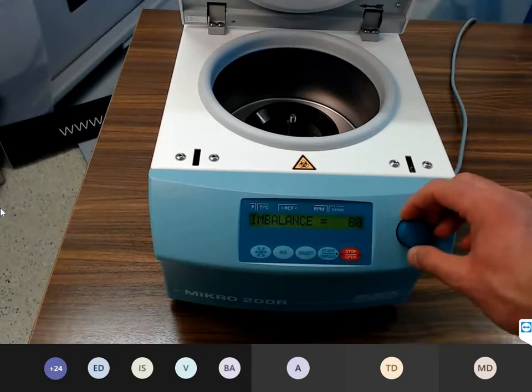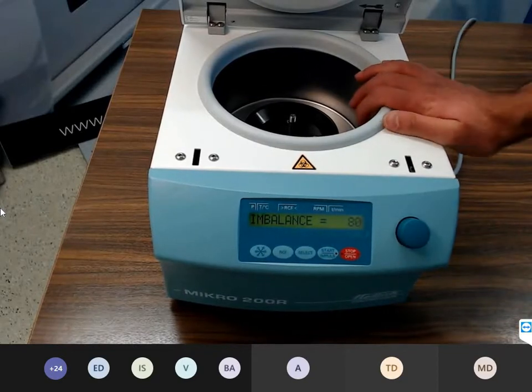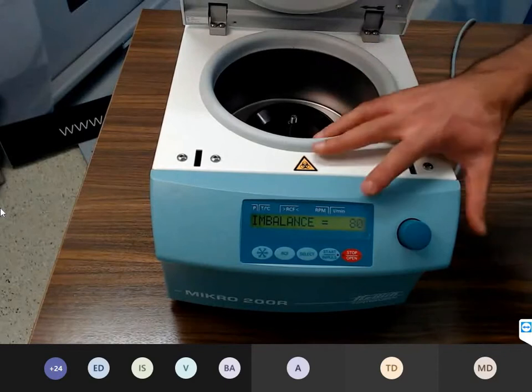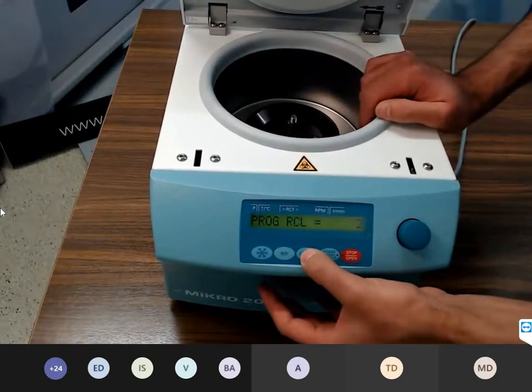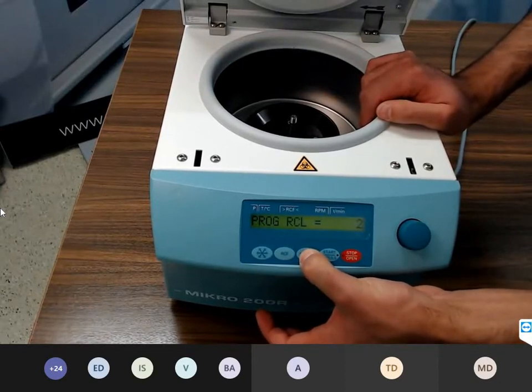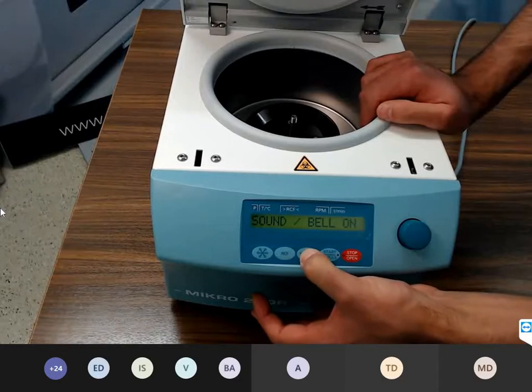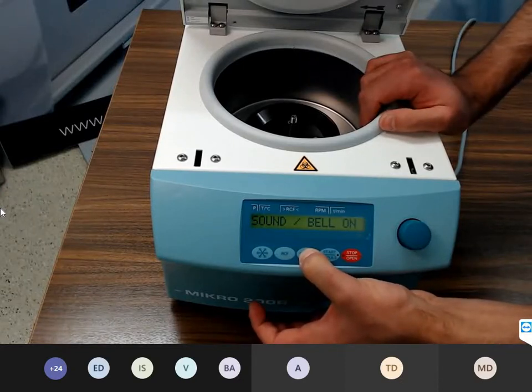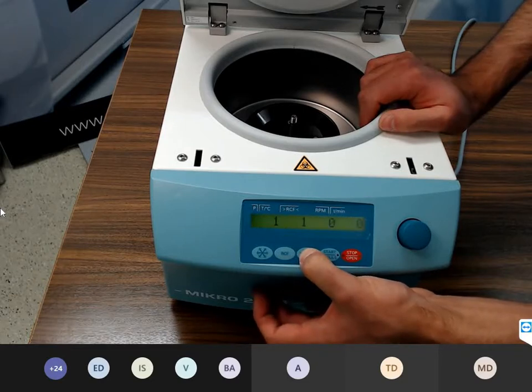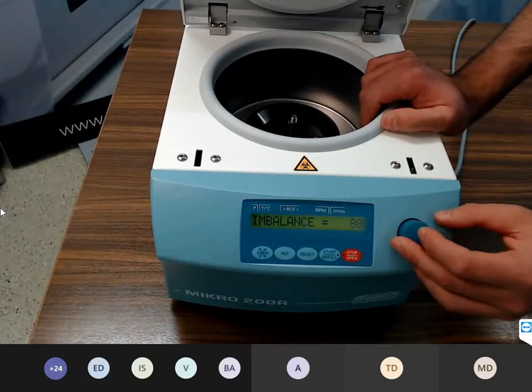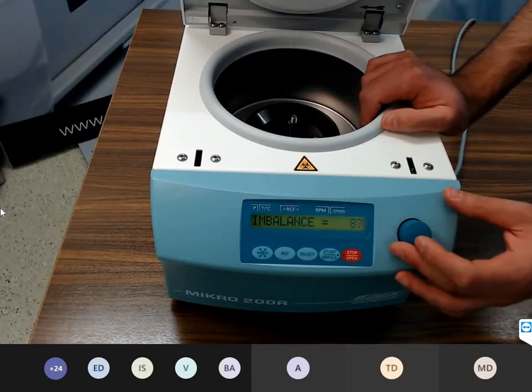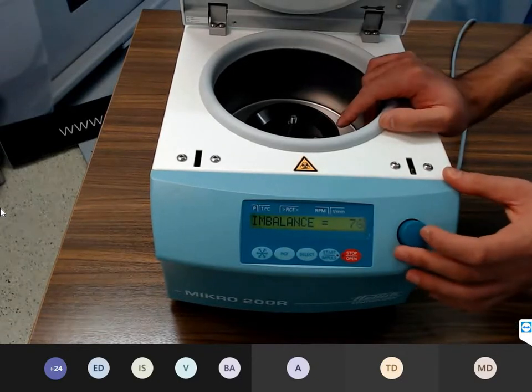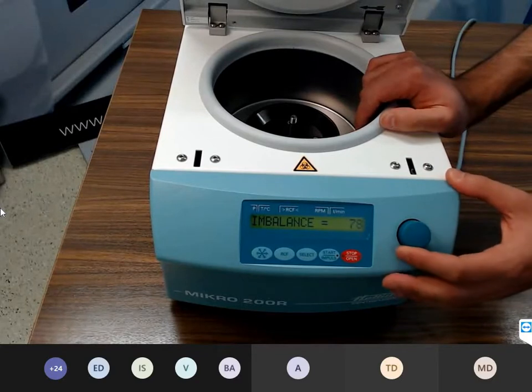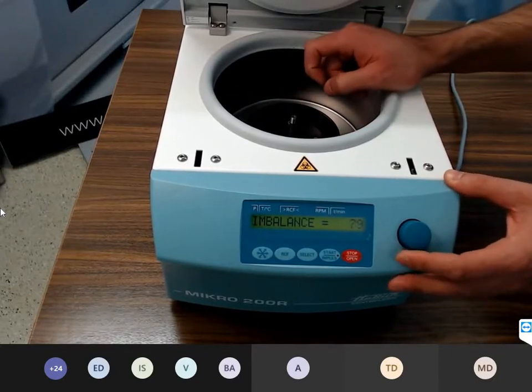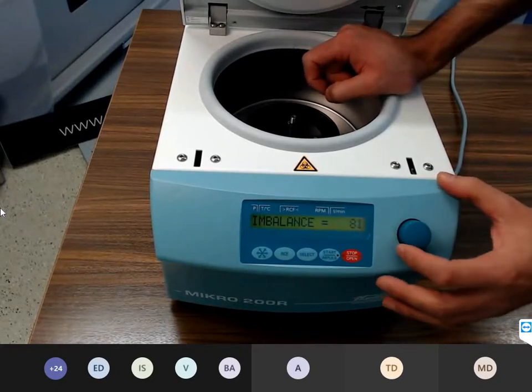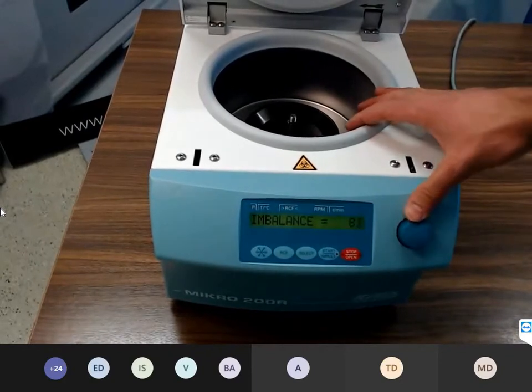Now we have here the imbalance. We have here an imbalance sensor on the bottom of the device. We can set it in percent. 100% means standard, and if you go higher, the device is more sensitive. If you go down, the imbalance is not so sensitive. You can set it. That means insert a weight, check it, and adjust this value here in percent. That is the imbalance setting.